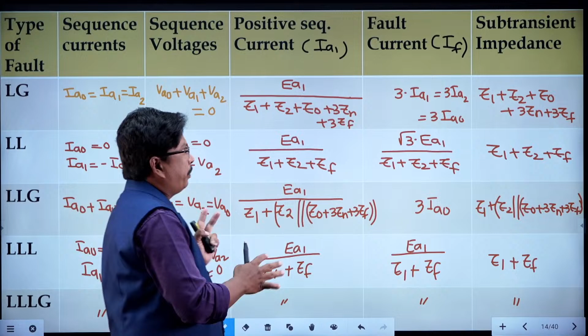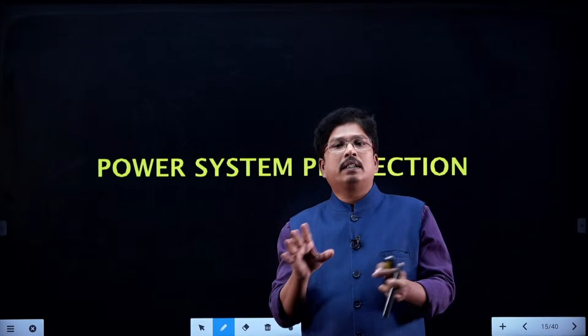First of all, what are the various elements in power system protection? What is power system protection? Why do we have to give protection to the system? The need of this switchgear and protection system is that it has to continuously monitor the entire power system network, and it has to ensure that there is no physical damage to any element from any abnormal condition. The abnormal conditions may be faults, any overloading condition, any underload condition, any lightning surges or switching surges, whatever it may be. The protection system has to ensure that there is no physical damage to the power system elements. What are power system elements? Power system elements means generators, transformers, transmission lines and the loads. Any element should never be damaged. That is the duty of the power system protection equipment.